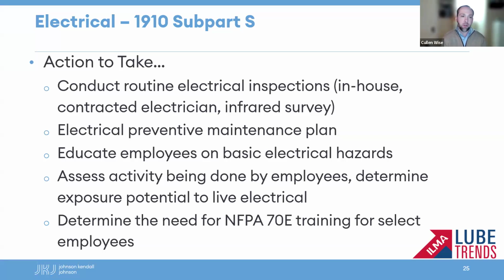They have to take the front of the electrical panels off, so they need to be qualified to do that. They need to have protective equipment to do that. Infrared surveys, we typically suggest about every couple of years. NFPA recently increased the frequency, and NFPA says they should be done annually. That is not a requirement. That's not a reference by OSHA. It's just a best practice.